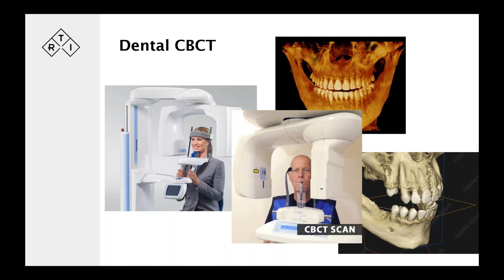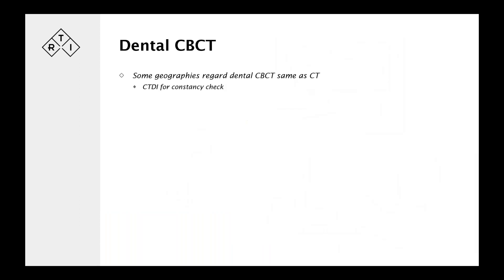Dental CBCT looks a little bit like panoramic dental, but the difference is that instead of a fan beam, it's a cone beam that generates a full 3D image of the patient's dental areas. It is CT, and thereby in many areas it's regarded as a normal CT scanner. Requirements for QA and regulatory measurements are the same as for a normal CT scanner in a hospital, but there are some question marks when it comes to dental CBCT as to the relevance or appropriateness of treating it exactly like a CT.